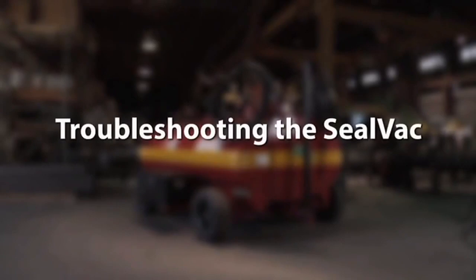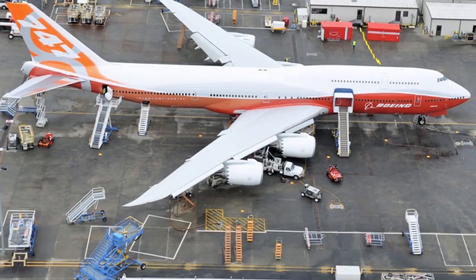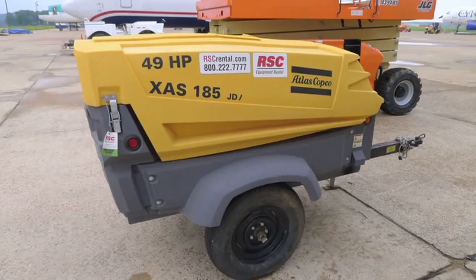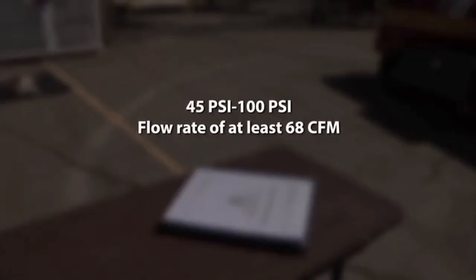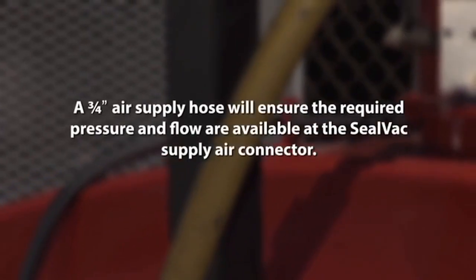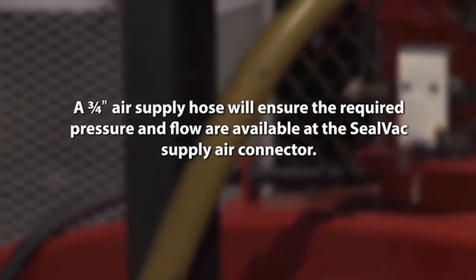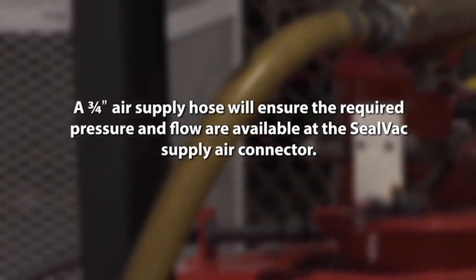Troubleshooting the SealVac. The SealVac has proven to be a very dependable piece of maintenance equipment. Experience shows us that the majority of the time, problems can be traced back to the air source. If the SealVac is performing poorly, ensure the air source meets the required specifications. Once again presented here for emphasis: 45 psi minimum to 100 psi maximum, with a flow rate of at least 68 CFM. A 3/4-inch air supply hose will ensure the required pressure and flow are available at the SealVac supply air connector.